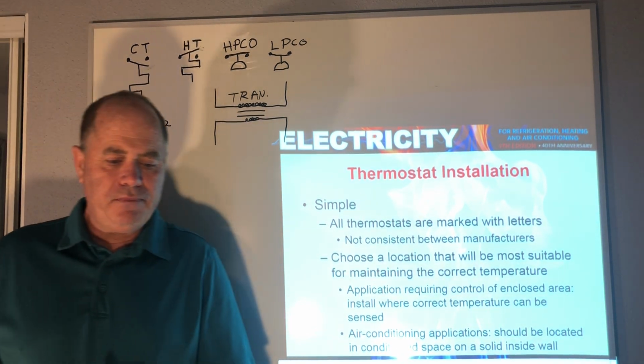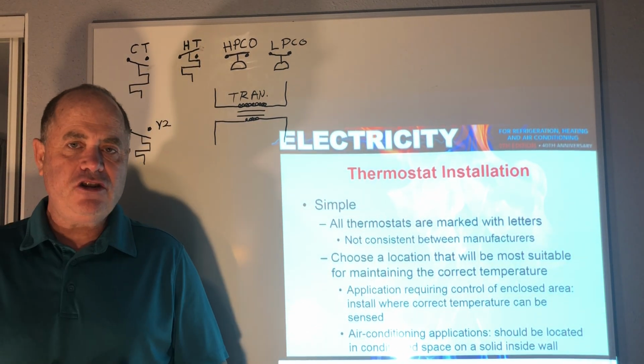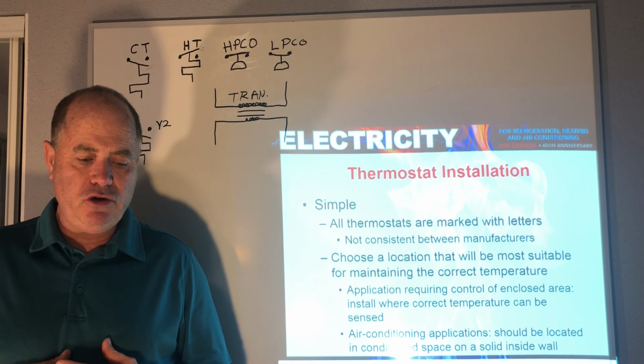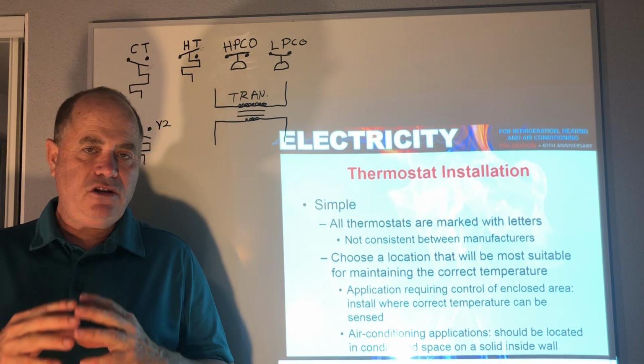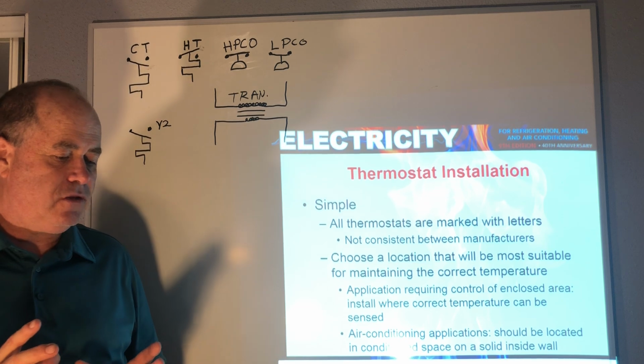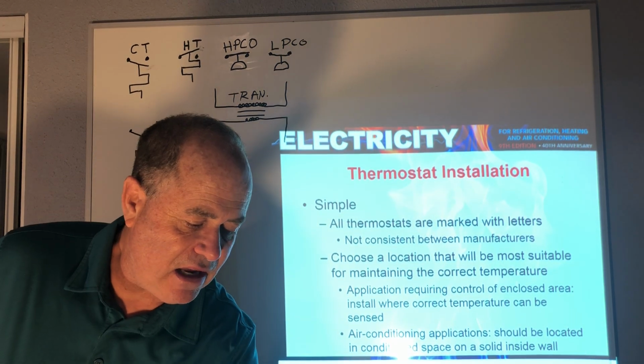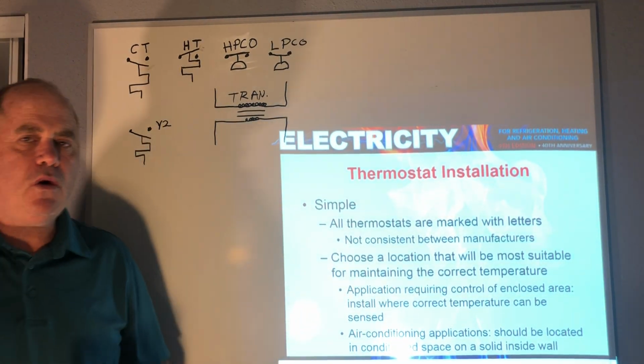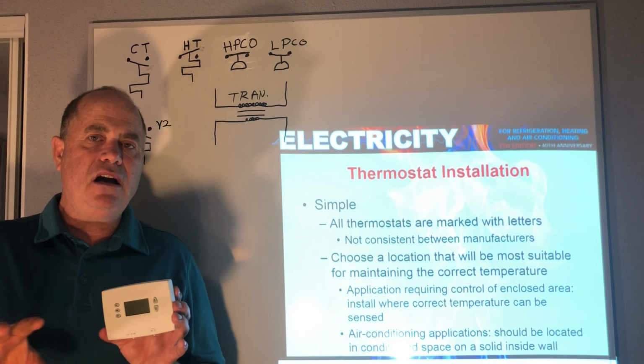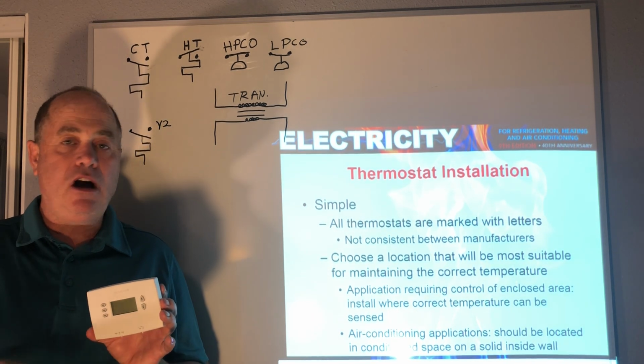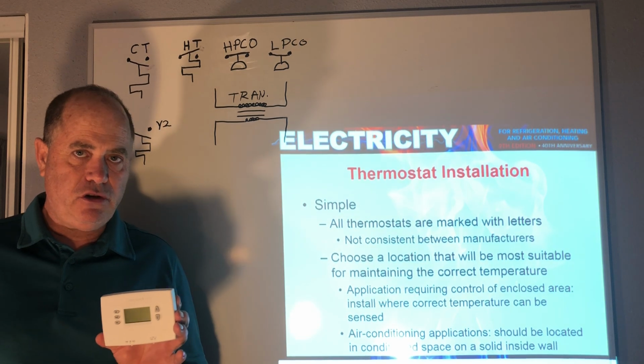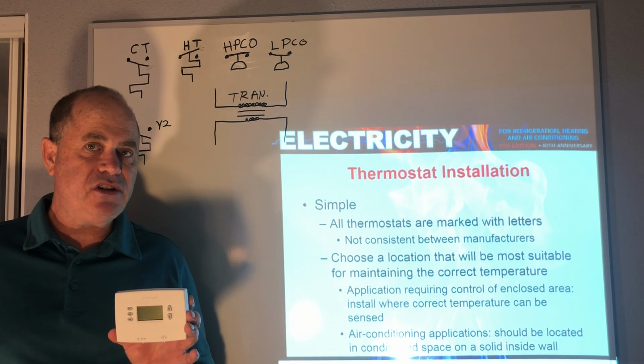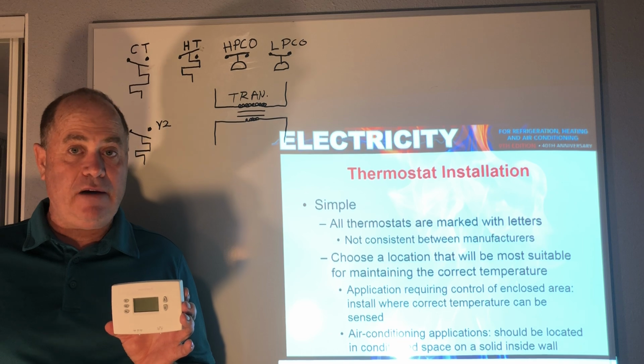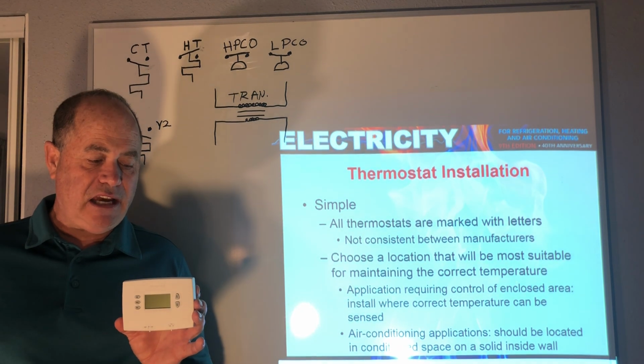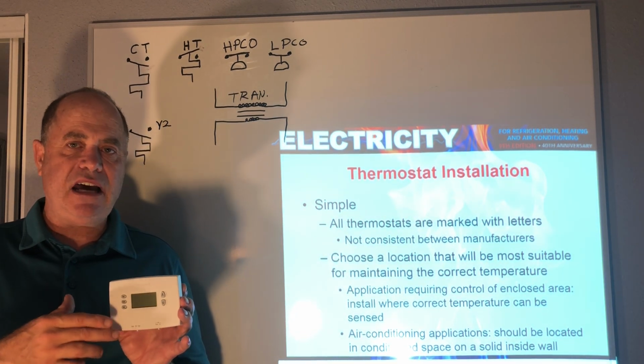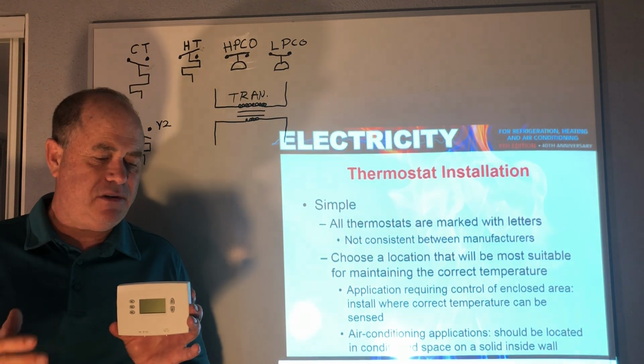Now, thermostat installation is pretty simple, just usually a couple of screws. And again, you want to choose a suitable location for a thermostat. Generally for a home, you want it to be near the return air, not in a specific room, but in a common area of the house near the return air, not near a heat source like an appliance, a coffee pot, a window that can let light in to shine directly on the thermostat, or anything like that, because it'll fake the thermostat out.